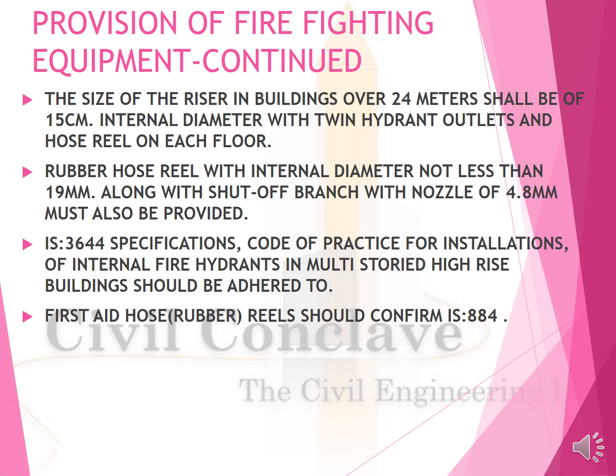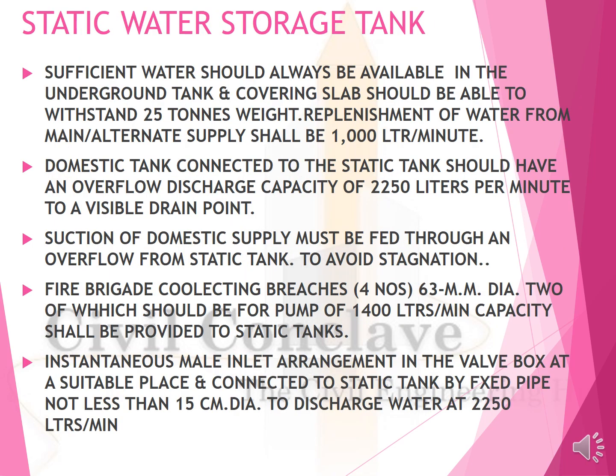Provision of firefighting equipment. The size of the risers of buildings more than 24 meters should be 15 centimeters. A rubber hose reel of not less than 19 mm, along with a shut-off branch nozzle of 4.8 mm, is also to be provided. Refer to IS 3644 for the specification. First aid hose reels to conform to IS 884. Static water tank. Sufficient water should be available in the underground tank and the covering slab should withstand 25 tons weight.